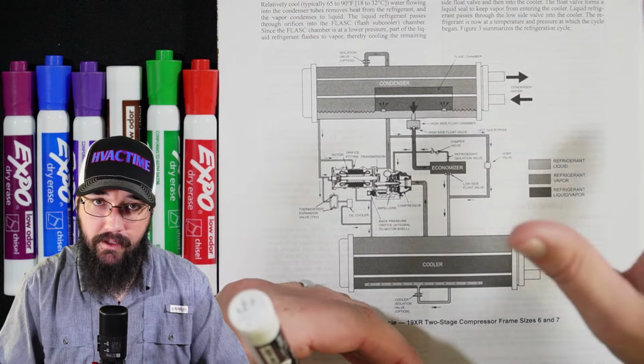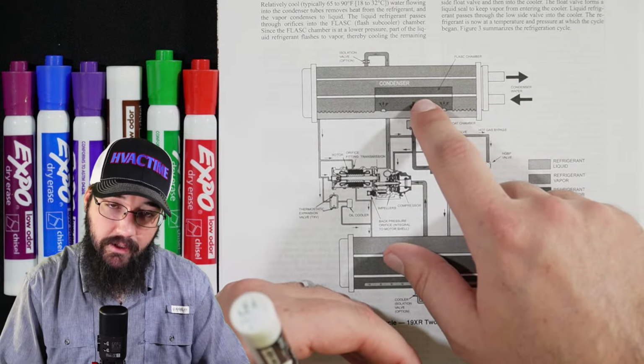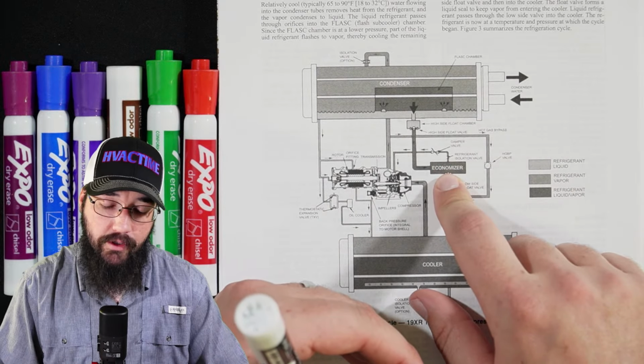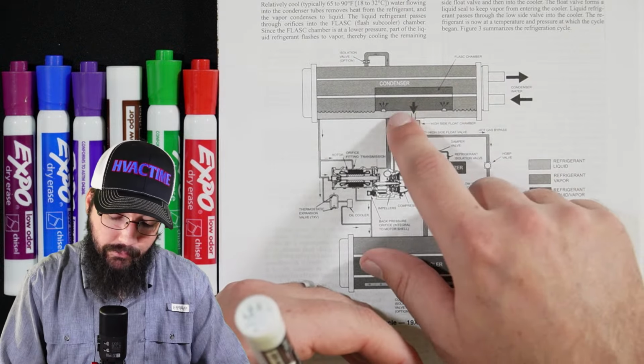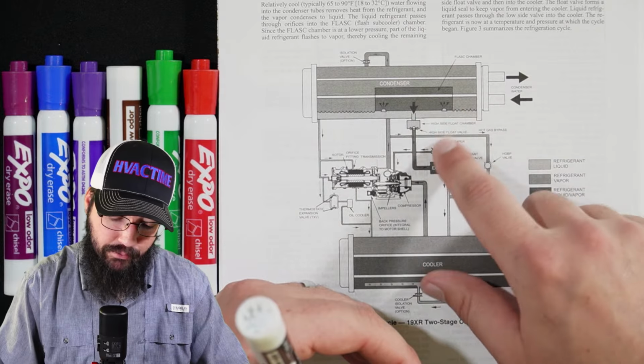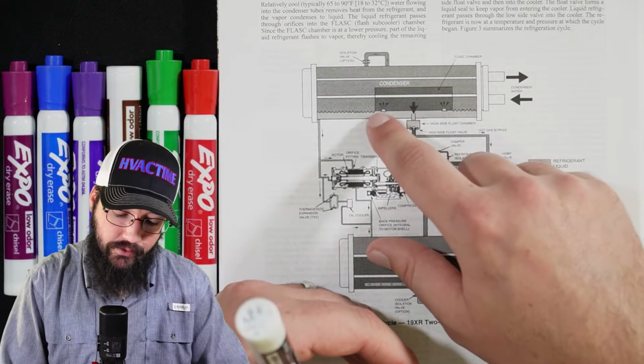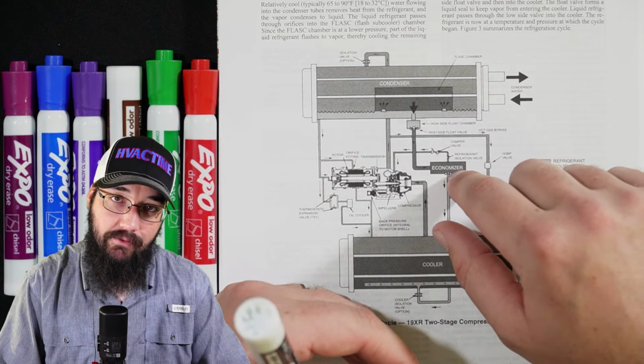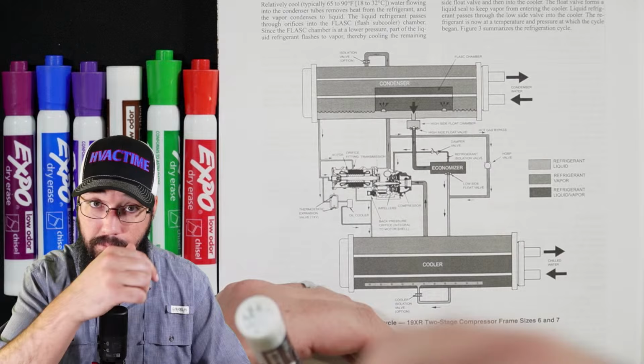So in this particular case, this would be our medium high pressure. Now we start blending into like a CVH world here, where we have medium high and medium low pressure, and then we have our low and high. Anyway, so we have kind of a medium high pressure with this economizer. If it didn't have the economizer, we would just call this our medium pressure zone.